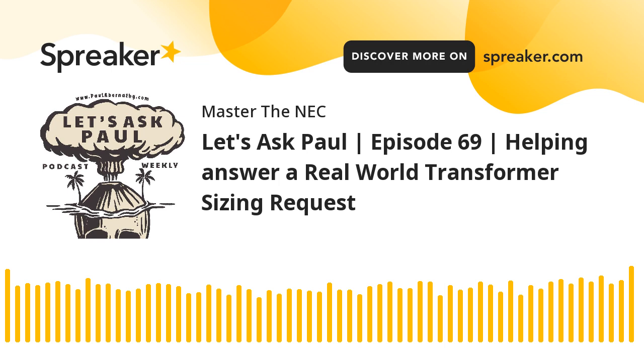Well, a 30 kVA transformer can handle 83 amps. Now, where do we get that? Again, we're assuming all of this is three-phase, and this is 208 volts, three-phase. So you take the 208 times 1.732, that gives us 360. And that's what we're going to use in our math. So if it's a 30,000 VA transformer, or 30 kVA, we just converted that into VA, and I'm going to divide that by 360. That's 83 amps. So a 30 kVA transformer can handle 83 amps.